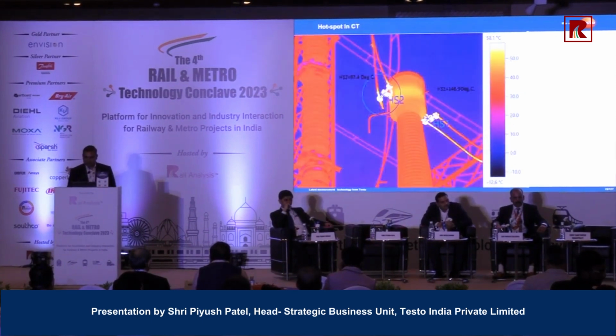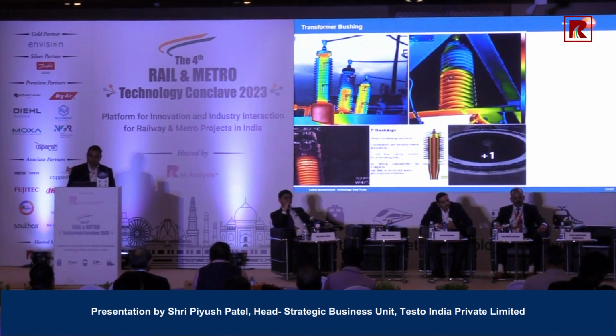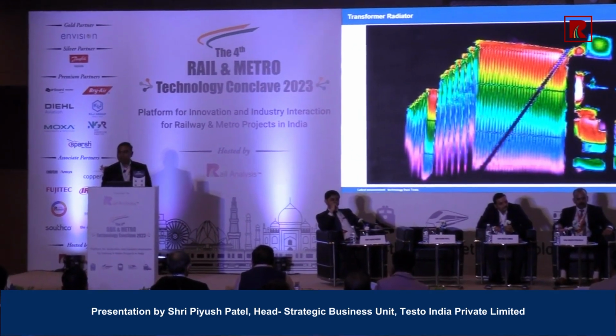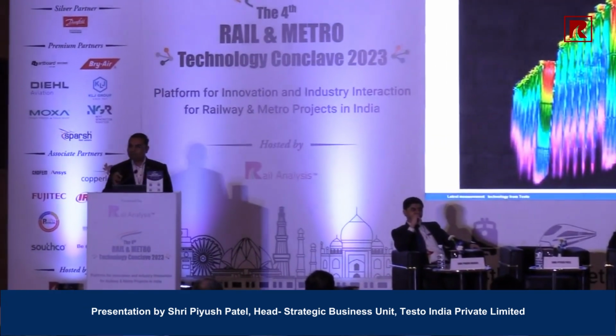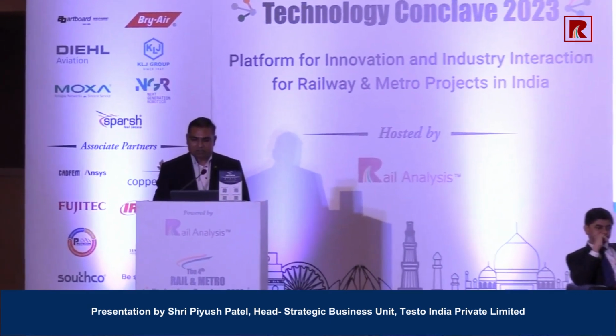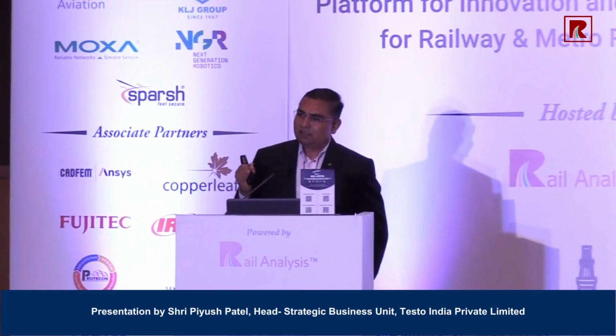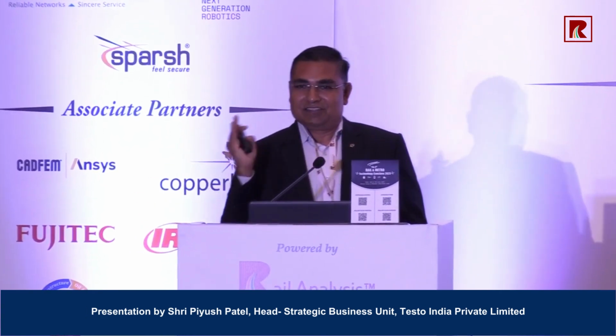Hotspots in CT, transformer bushings, radiators - these are also very important in substations. So when doing thermography even in windy areas versus normal conditions, we need to take care. Sometimes there is wind flow while we are doing thermography, and in that case we will not get the correct hotspot. So we need to do it in both conditions.